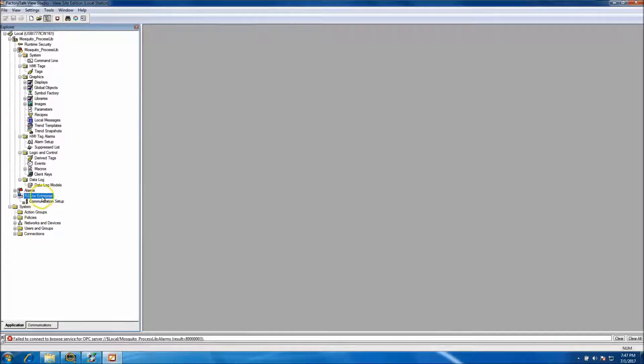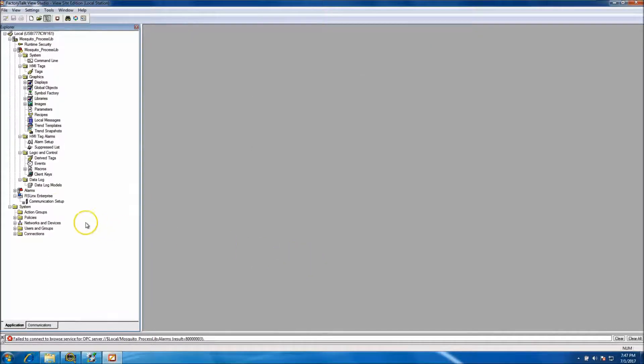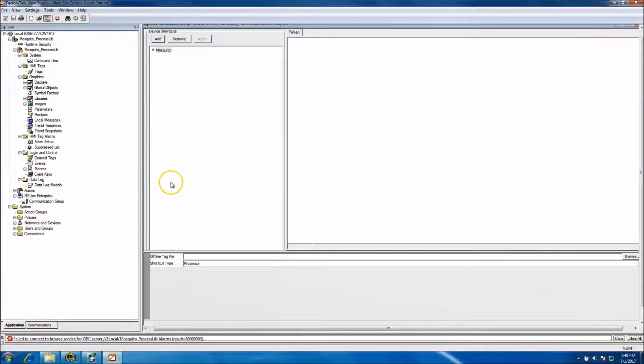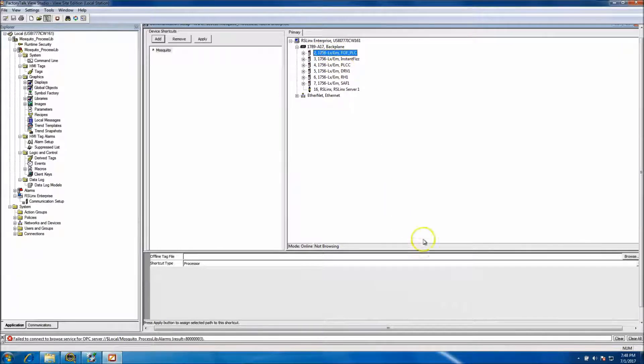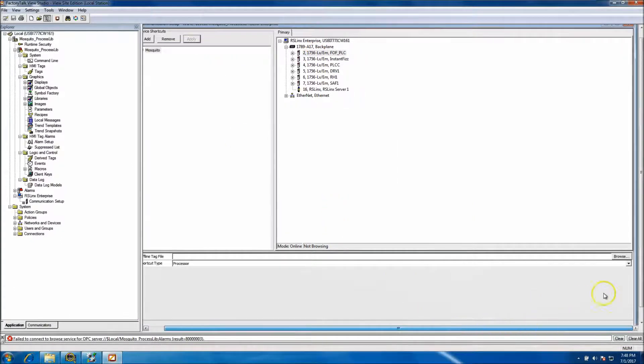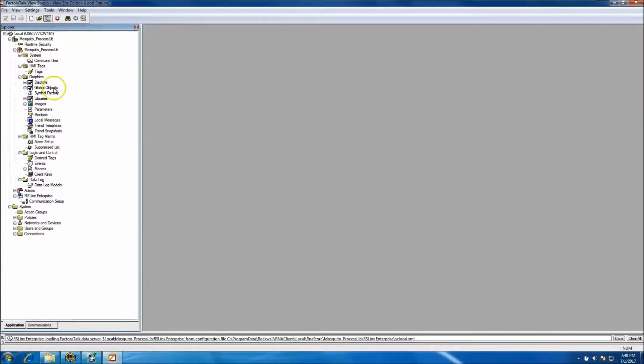Once the application loads, there are two major things you need to do. In RSLinx Enterprise, right-click and open Properties to verify it's not using alarms and events. Then open up Communication Setup under RSLinx. The shortcut already named for the application just needs to be pointed to your processor - in our case we're using the 1789 virtual backplane, slot 2. Select slot 2, hit Apply, accept changes, and verify at the bottom that the changes took.